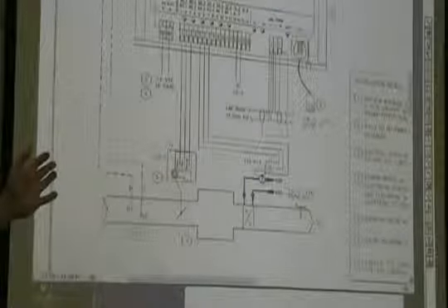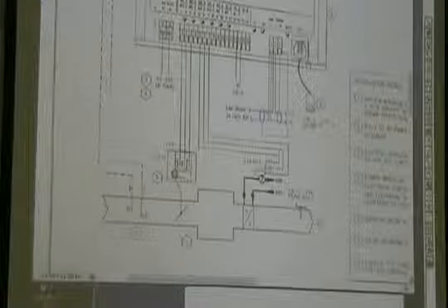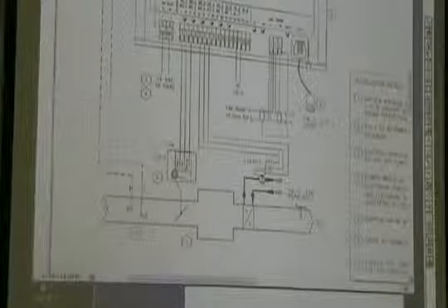For us, these TECs are great. They're beautiful, but all you've got to do is mess up one setting in them, and you've messed it up on several boxes. It'll cost us a lot of time. So you've got to be real careful when you're setting these things up. And if you don't know exactly what you need to put in there, just ask, because it can take a lot of time to go back and change that after the building's occupied, depending on what's wrong with it.